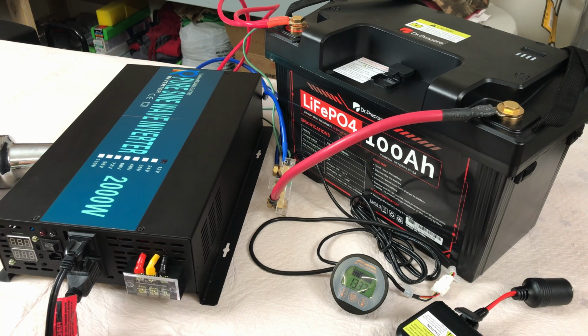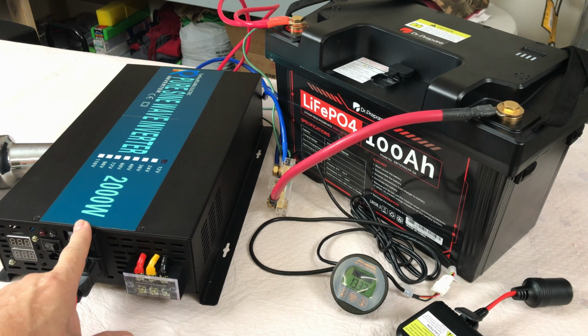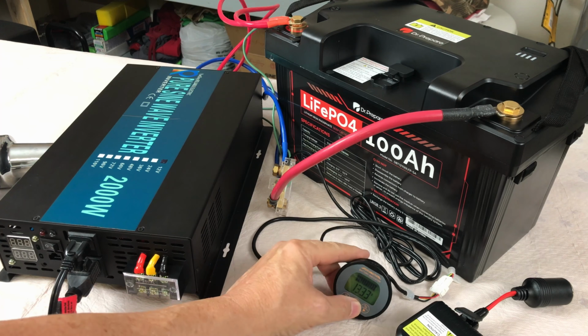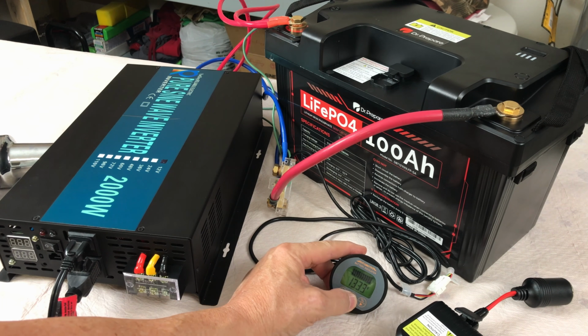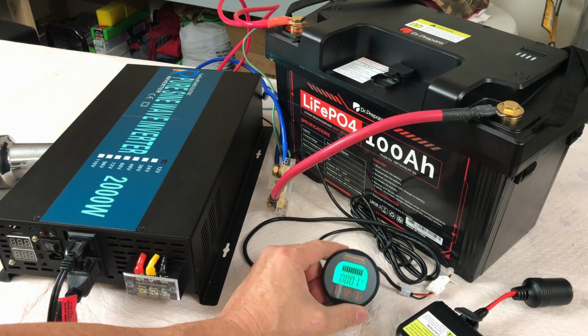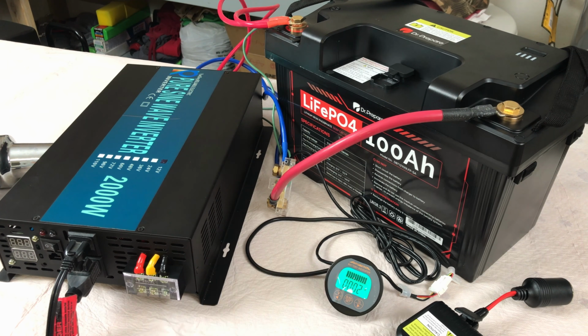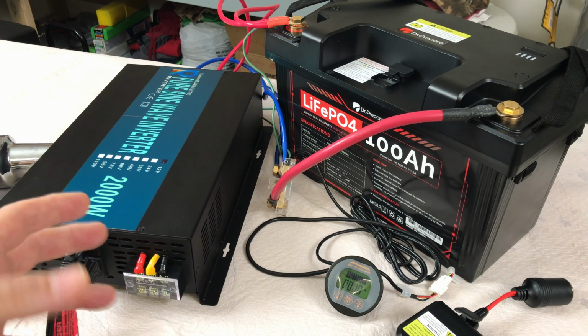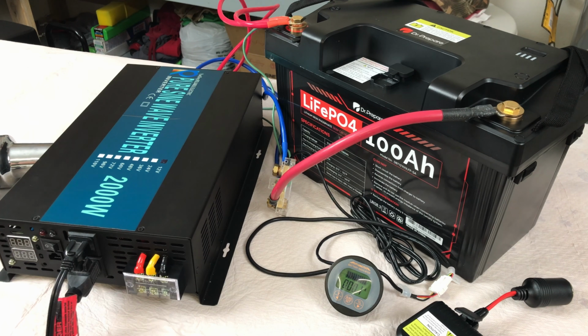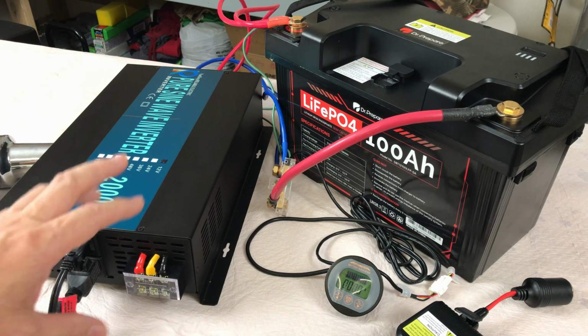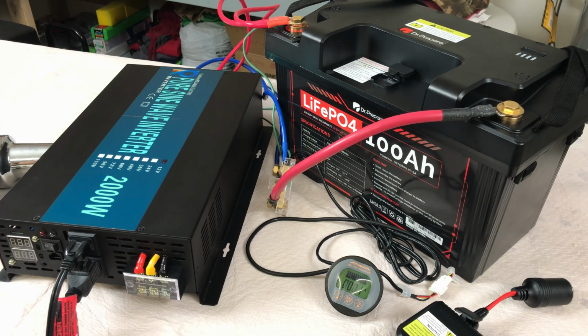It's going to be kind of noisy, but I'm going to turn on the shop vac first, and set this meter to show the amps coming out of the battery. Then I'll turn on the heat gun on low - we'll see what that does. That should bring it around to 80-85 amps. Then we'll go to full power, about 140 amps on the heat gun, and see if the BMS will shut down.